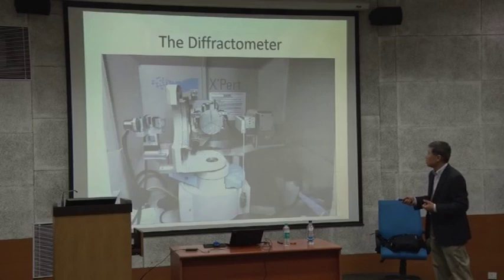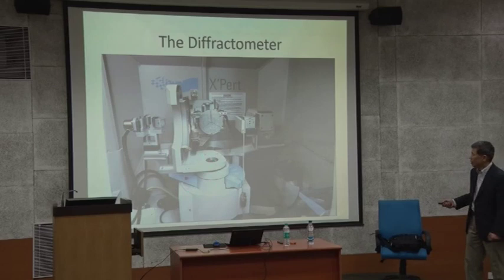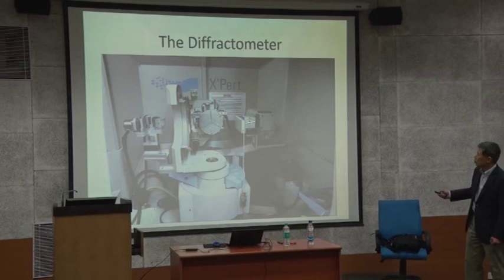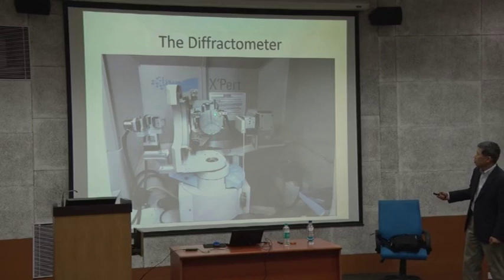This is actually a diffractometer commonly used for thin film diffraction. You have two circles attached to what we call a goniometer. The goniometer is normally your powder diffractometer in your labs here. There are two components: one is attached to the detector. This is a tube — actually an X-ray tube — and this is a detector. The detector itself moves at this angle, which is two-theta.